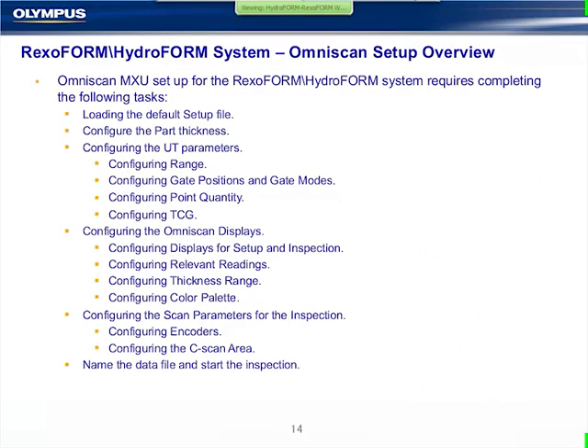So before we continue, that was a little bit about the hardware, about both systems, what separates them, water versus wedge. The actual setup for these is very similar. In fact, it's the same with one exception I'll point out about the synchronization feature of the HydroFORM. But what makes these applications somewhat of an entry-level phased array application is our ability to use one default setup file, make some minor changes to it to apply it to different thicknesses and diameters. So once you have the default file, it's pretty easy to see where the configuration is at for those of you who've been through OmniScan training, and make minor corrections.